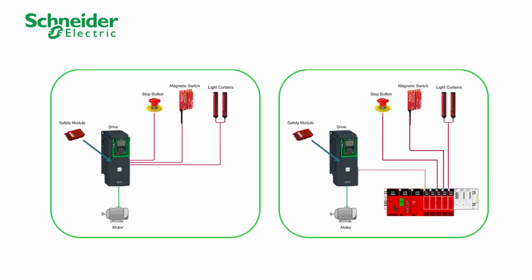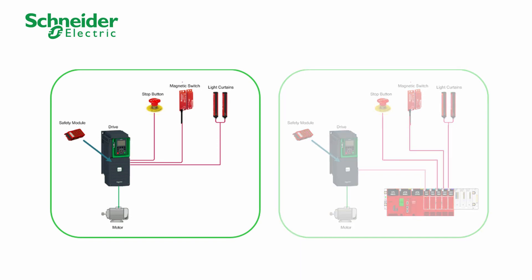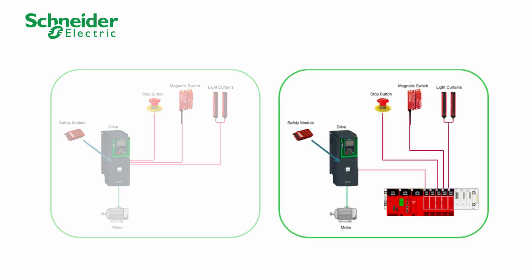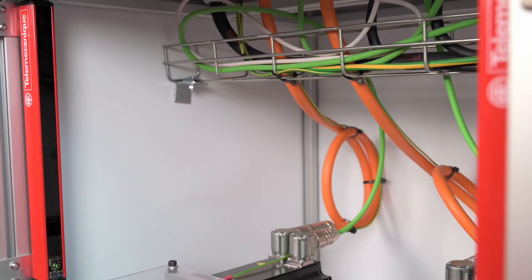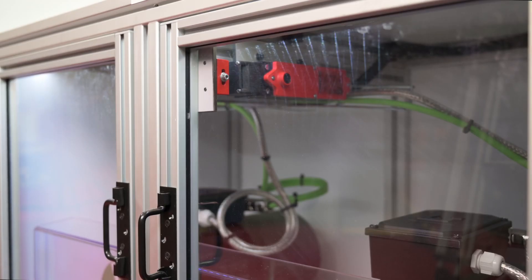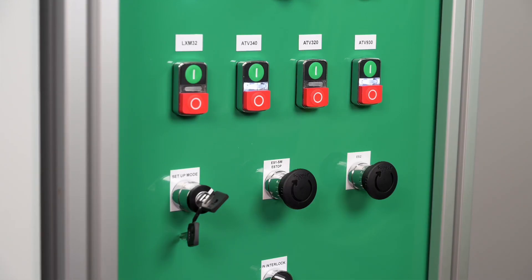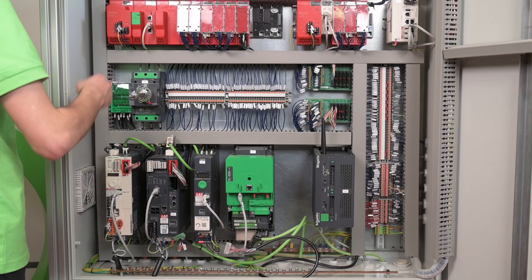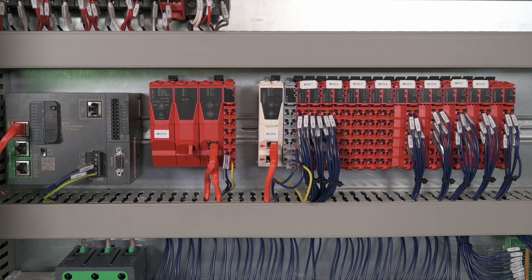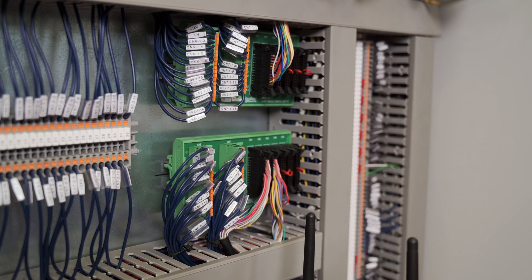There are two ways we can activate the safety functions. The first is by connecting the safety sensors directly to the safety module. The second possibility is by connecting sensors and the safety module to the M580 safety PLC. We have safety sensors like light curtains, safety limit switches, and emergency stops, connected through terminal adapters via the safety PLC or directly.